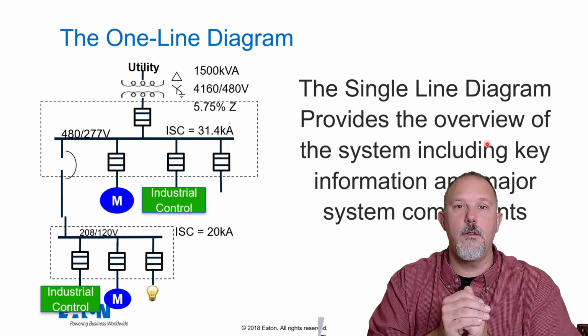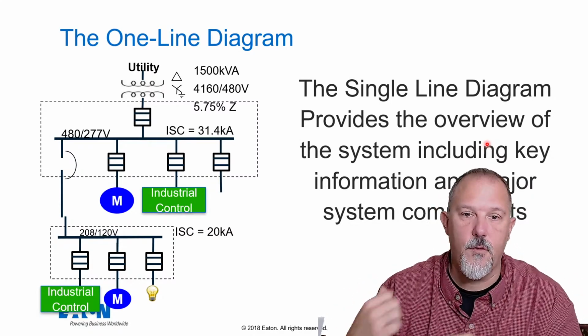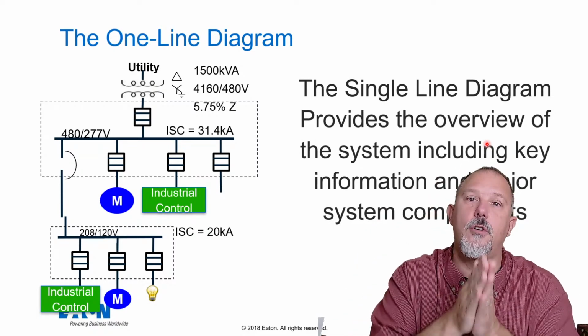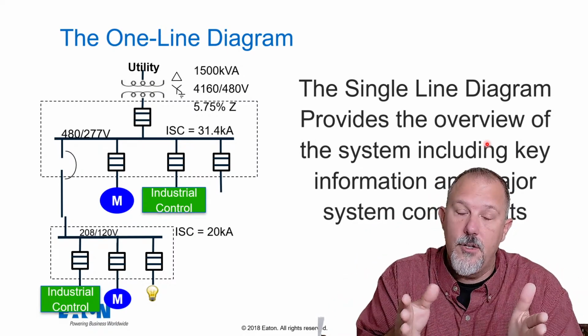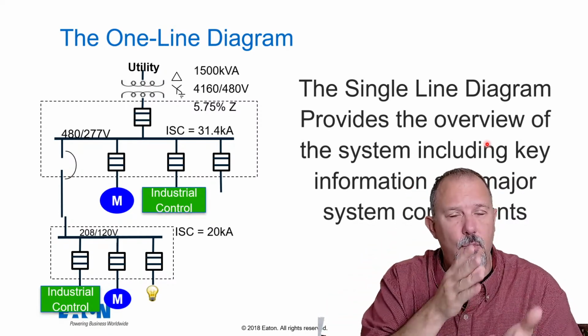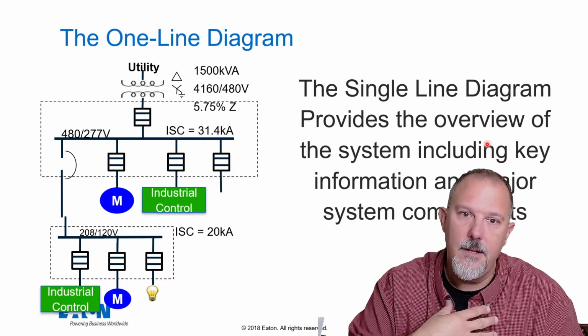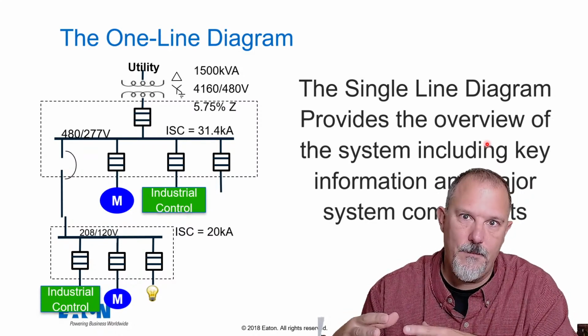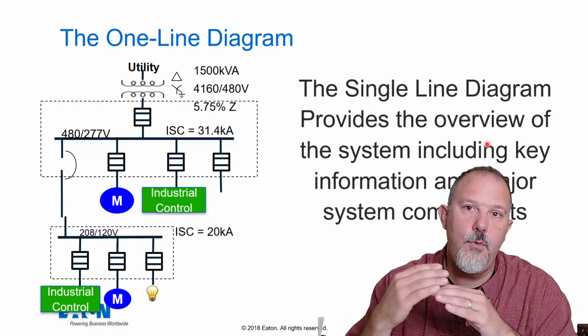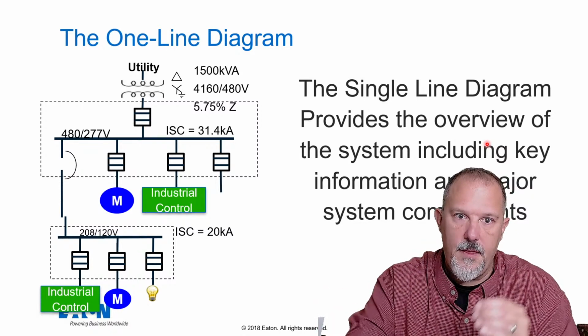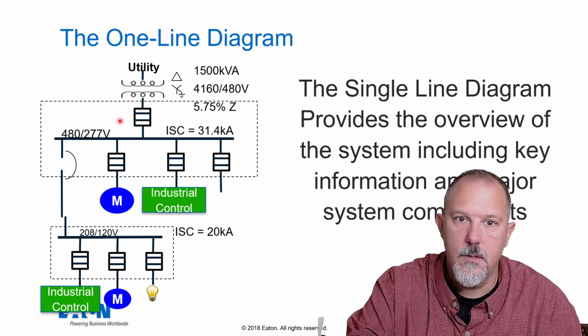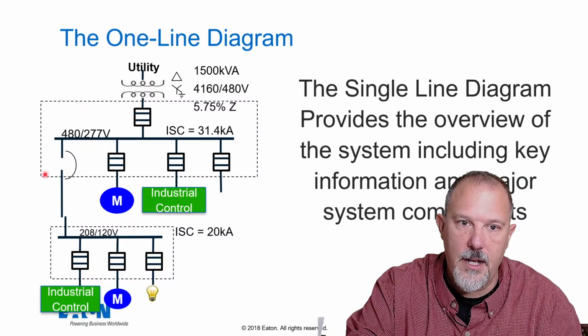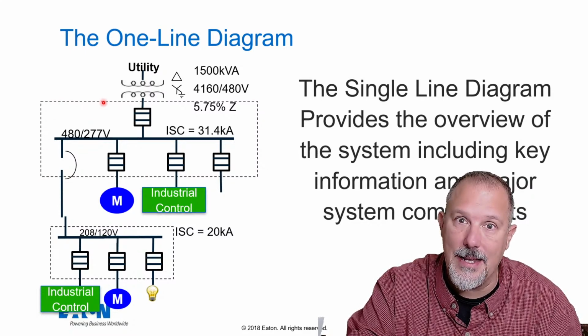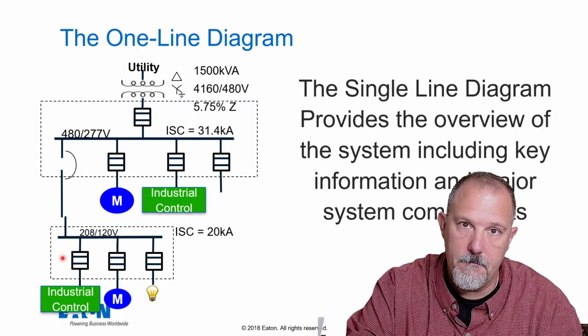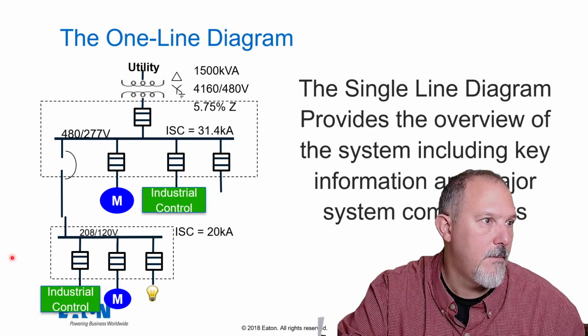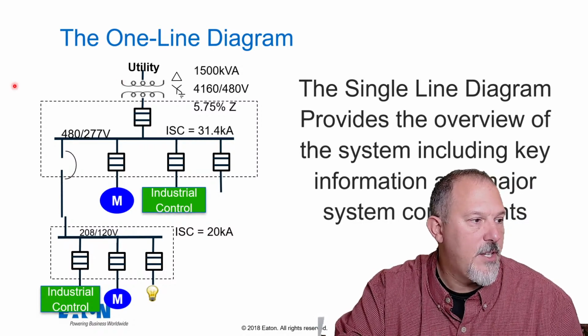If that's a circuit breaker, now my bets are off for that 20,000 amps, because that circuit breaker could start to add impedance and start to open. So I've got to be very, very careful. You must, in my opinion, limit your exposure to risk of screwing up by understanding that this primary fuse is only going to get you anything for the equipment that it's protecting, that it's inside of, nothing downstream. Just keep that in mind. That's opinion by Tom.